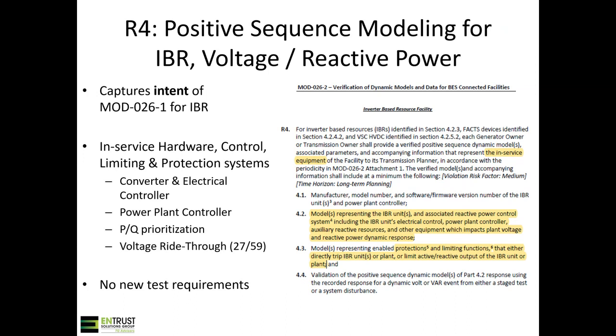In synchronous machines, your excitation system controls voltage and reactive power, your turbine governor controls frequency and active power, so they're decoupled to a large extent. It's really not that way for inverter-based resources — these devices themselves are converters, voltage source converters. They're programmed to deliver active and reactive power, and those loops are interdependent, because how an inverter is rated is by its output MVA, its output current. So sometimes you have to prioritize. You're sourcing this current from the same point, it's just that the controls have to independently treat how the power system views this current — active and reactive power. A little bit down the technical rabbit hole, but just to say that a lot of these features dealing with that type of control need to be represented.